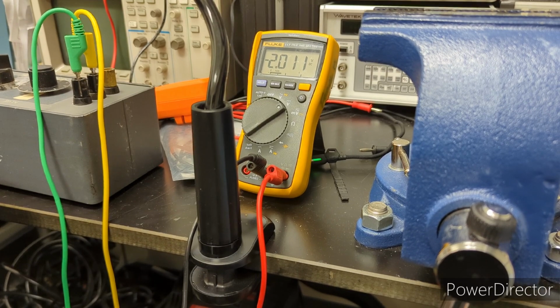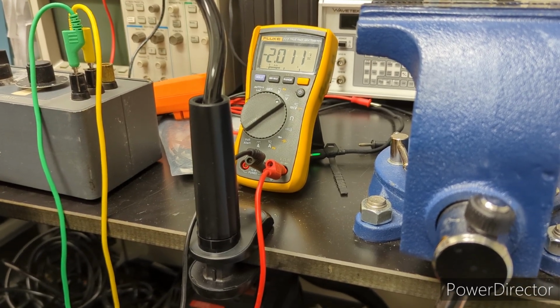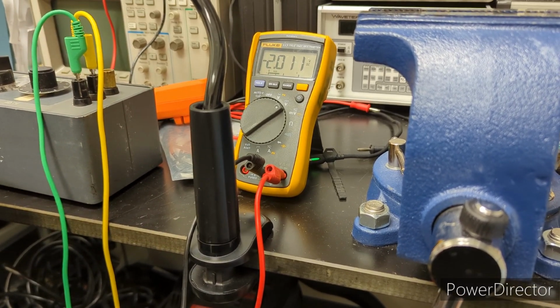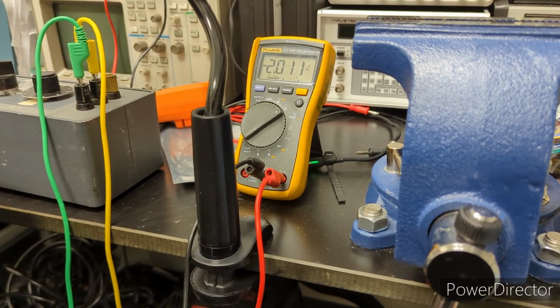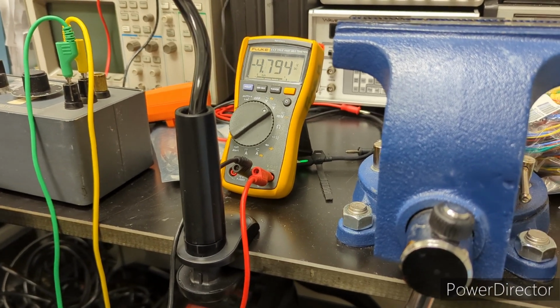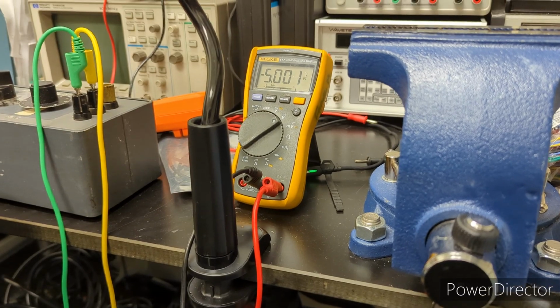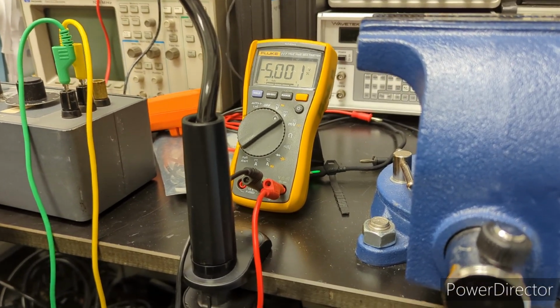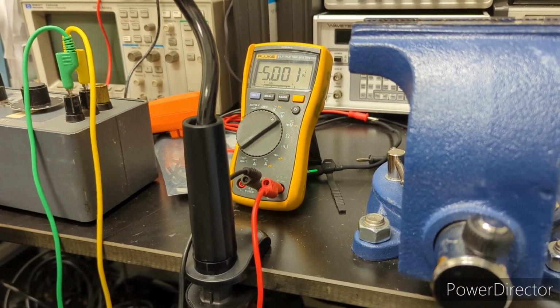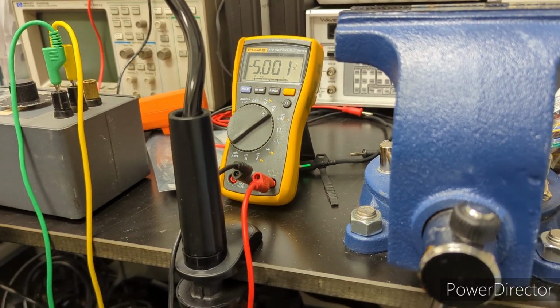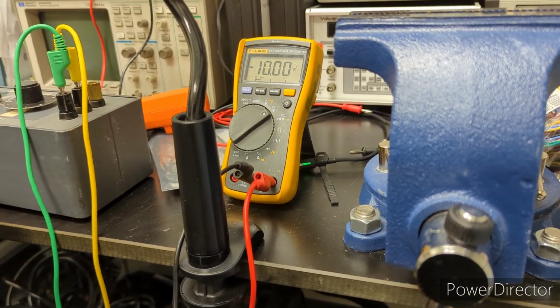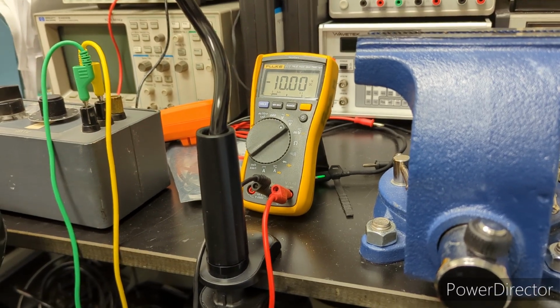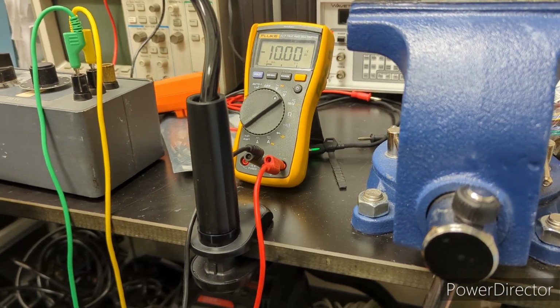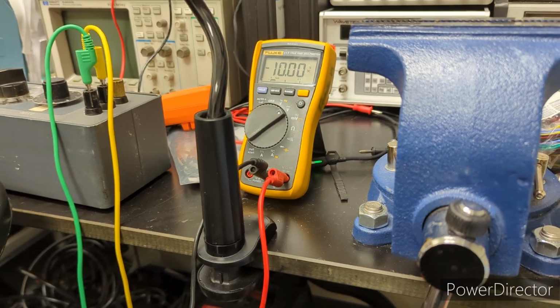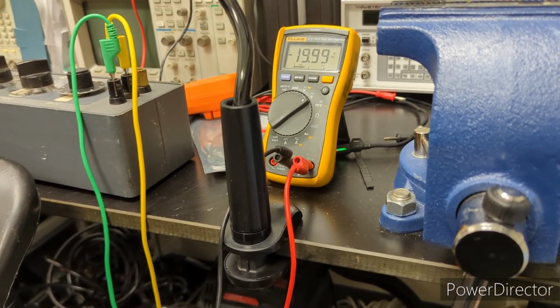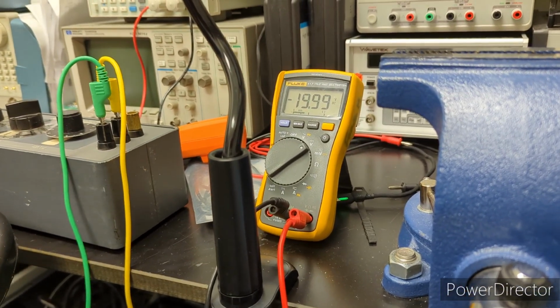0.2 volts, we should be seeing 2 volts on the meter, plus or minus 0.04, also good. 0.5 volts should be 5 volts on the meter, plus or minus 0.1, very good. 1 volt on the switch, 10 volts on the meter, plus or minus 0.2 volts, again really good. And finally, 2 volts on the switch, 20 volts on the meter.